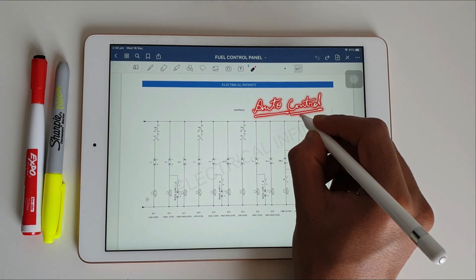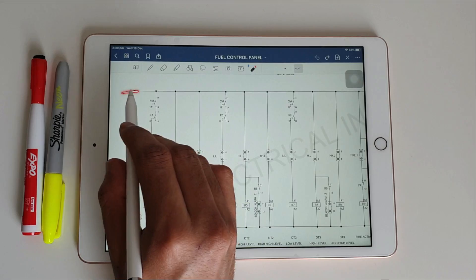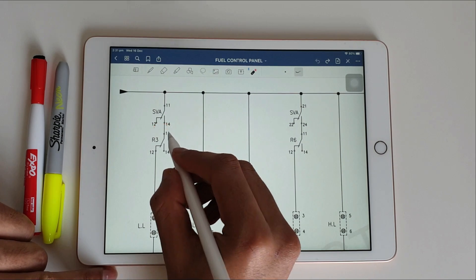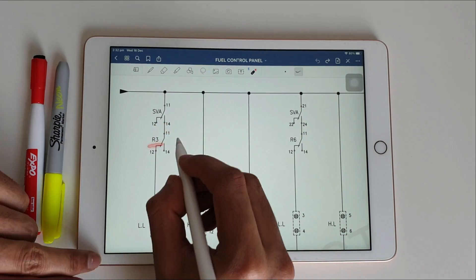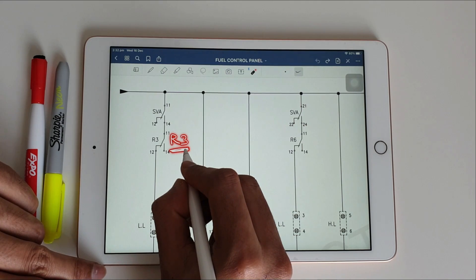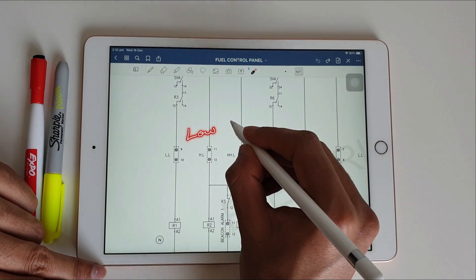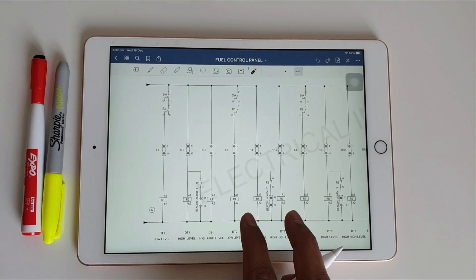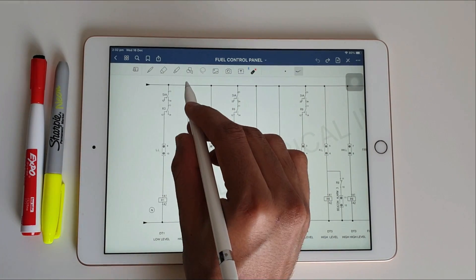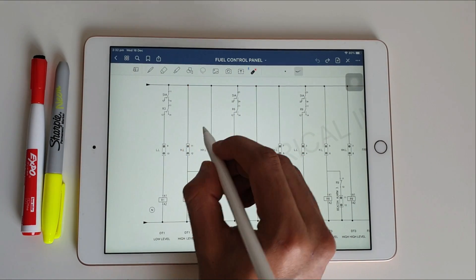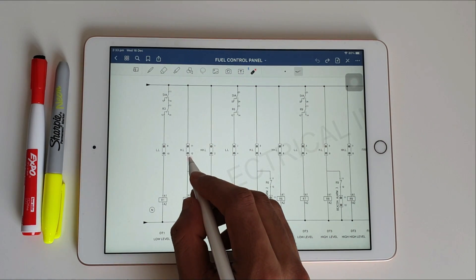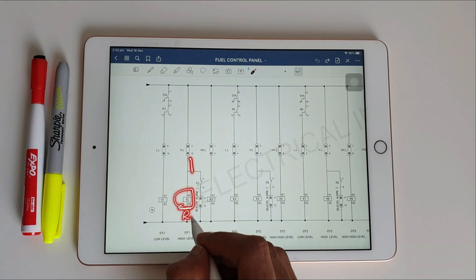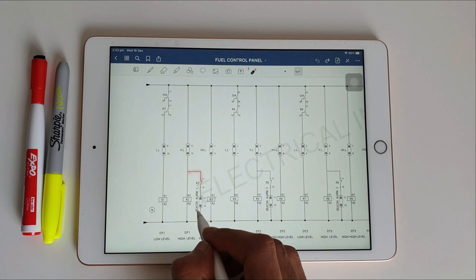In the auto control circuit, when the fuel tank level is low, a value is received from the sensors and the NO contact of the SVA terminal becomes NC, as does the R3 relay. This connects to the low level fuse, then to the R1 relay, which leads to turning on the solenoid valve so fuel is pumped to tank one. The second branch is used for high level fuel indication and for turning off the pump.